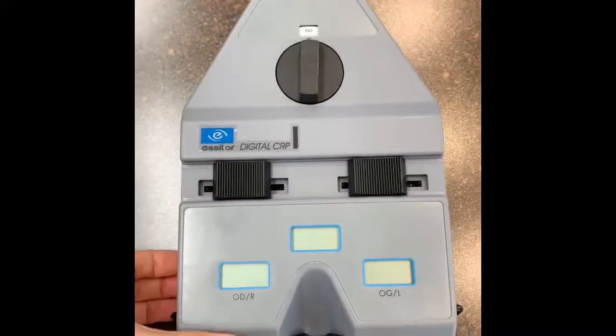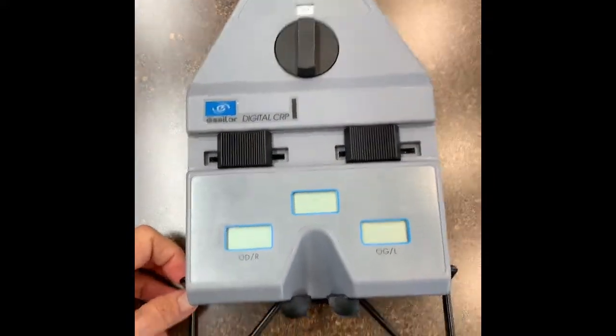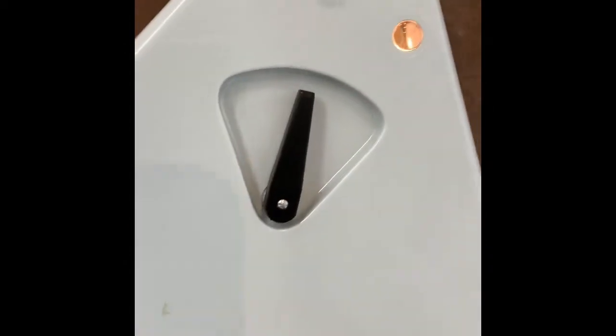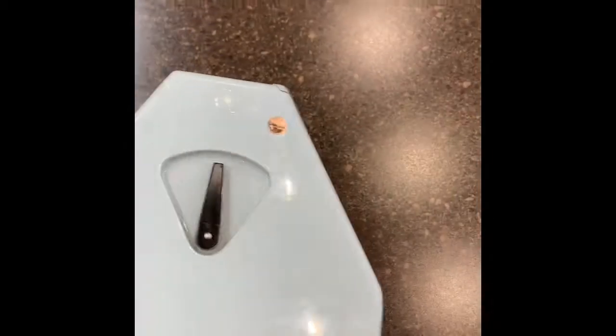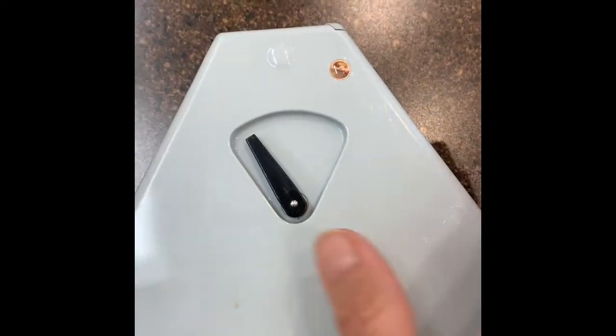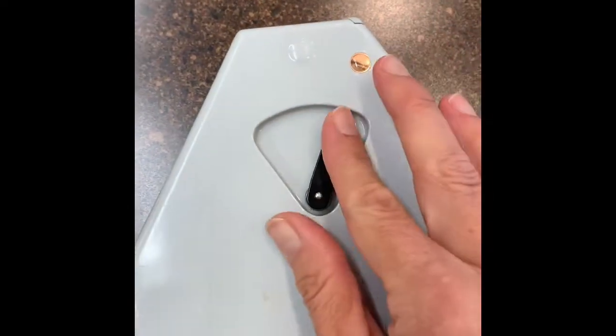Today we're going to train on how to use the Essilor Digital CRP Pupilometer. When this light comes on, it is turned on and ready to go. This controls whether you do right eye, left eye, or both.